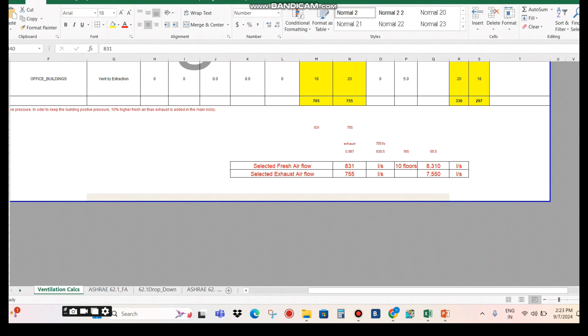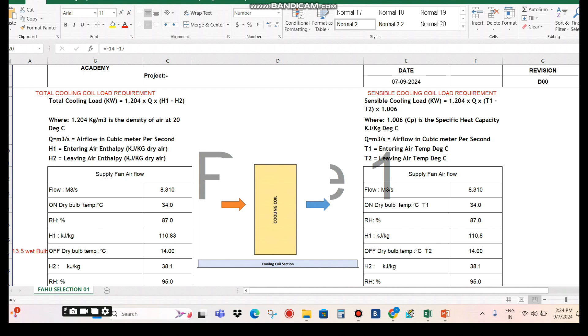In the last video we found that the total fresh air flow for the floor is 831 liters per second and the exhaust air flow is 755 liters per second. Considering the same arrangement for 10 floors, multiplying by 10 gives us 8,310 liters per second and 7,550 liters per second. We are now going to select one FAHU with this supply air flow. In the Excel file, I entered the flow in cubic meters per second: 8,310 divided by 1,000 gives 8.310 m³/s.